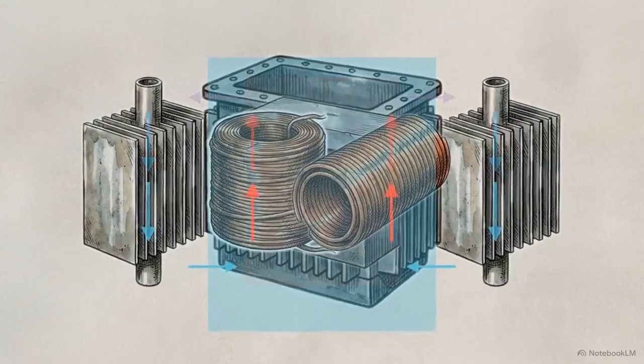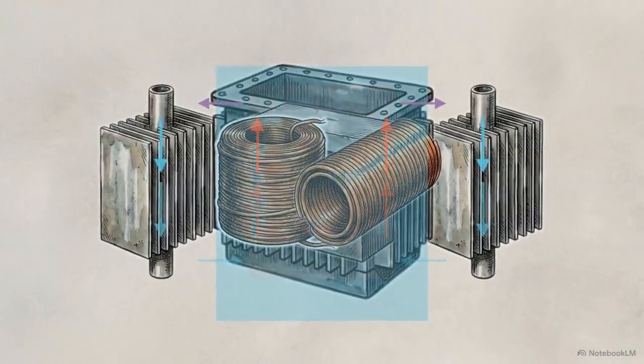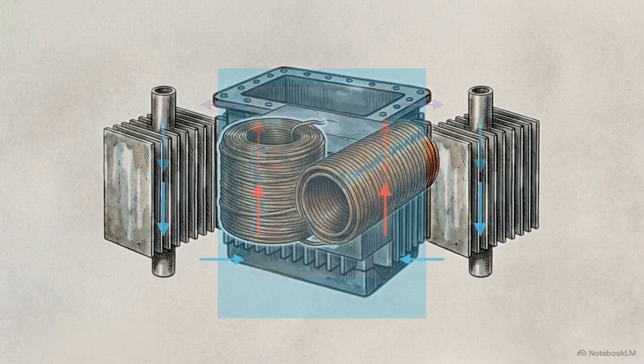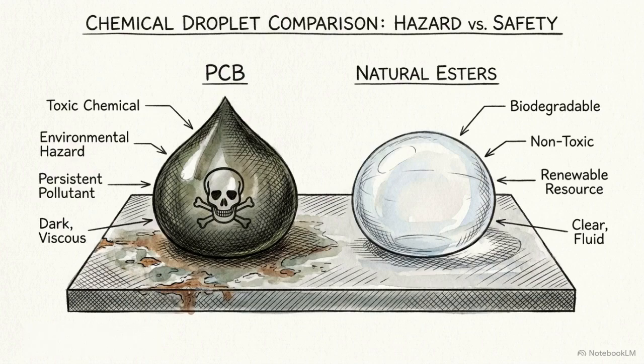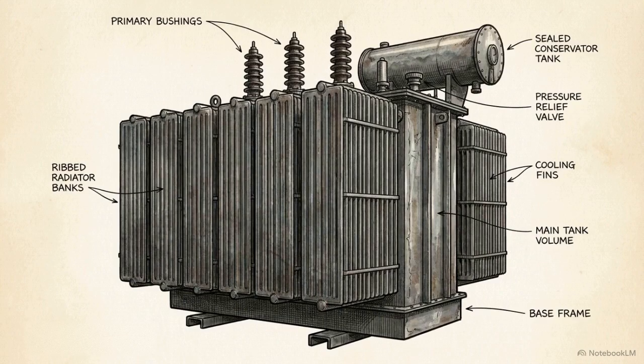It is also a dielectric insulator. With a breakdown voltage exceeding 28 kilovolts, the oil prevents electrical arcs between the high-voltage coils. Modern units have transitioned from toxic PCBs to biodegradable natural esters that offer high fire points and stable dielectric properties. Without this chemical bath, the thermodynamic stresses of grid-scale transmission would destroy the machine.